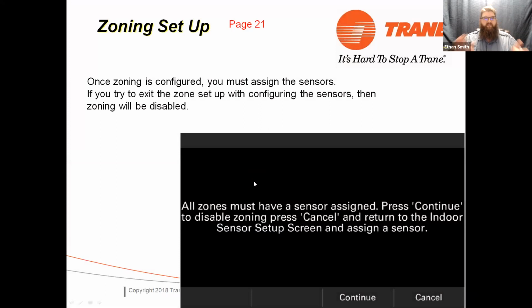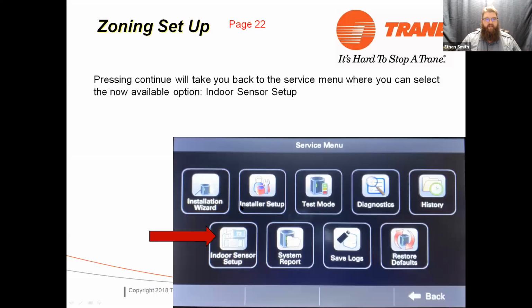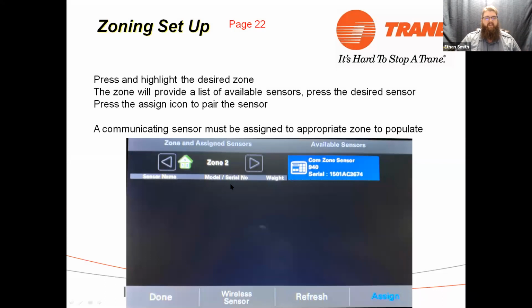The thing to be aware of is once you've done all that in zoning, you've selected your voting zones, you've selected your limits, it's going to give you this screen that says you must assign the sensors. If you exit the installer setup screens without assigning sensors, it's going to disable your zoning. Okay, so you're going to go ahead and hit continue right here. It will take you to the service menu where you will now see an indoor sensor setup button. If you click on that, you'll have a list of zones.